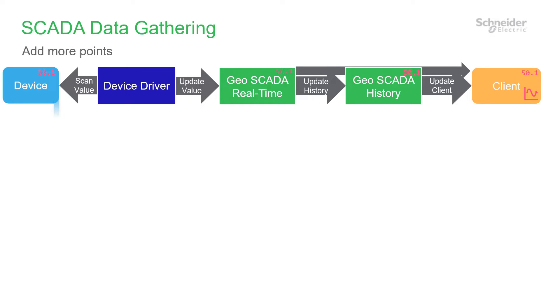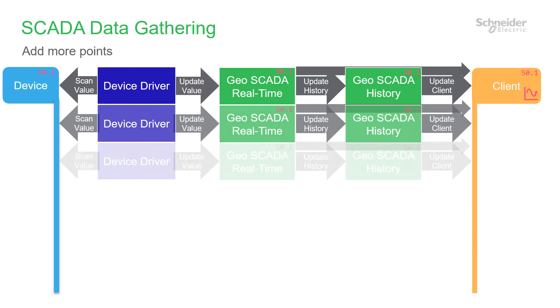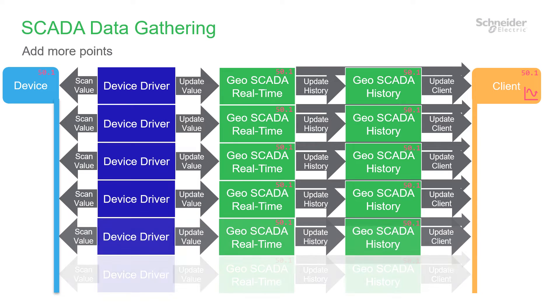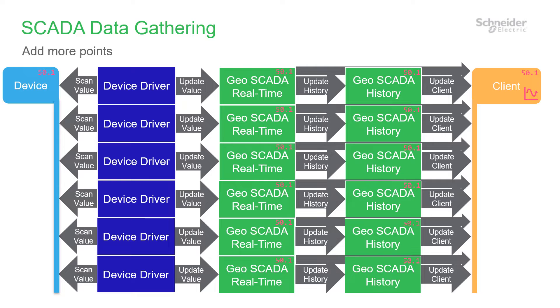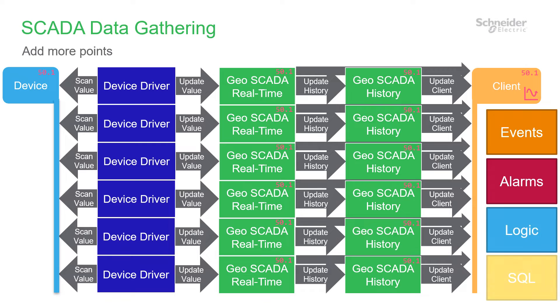There's a big problem with this when you want to scale it up. We're often reporting the same values over and over again for no good reason. This also uses networking, storage and CPU and just will not scale. So please don't do this with GeoScada. If you add on event storage, alarm handling, logic and derived data and SQL queries, there'll then be an overload of redundant activity, slowing your system down.